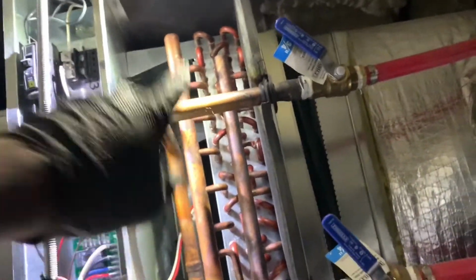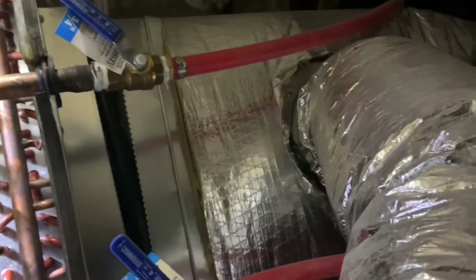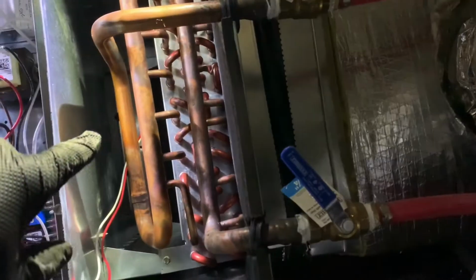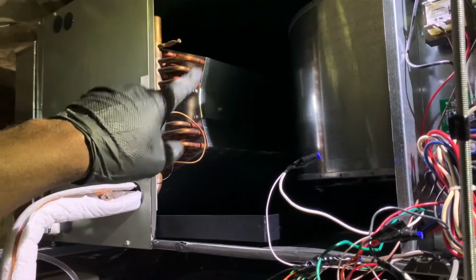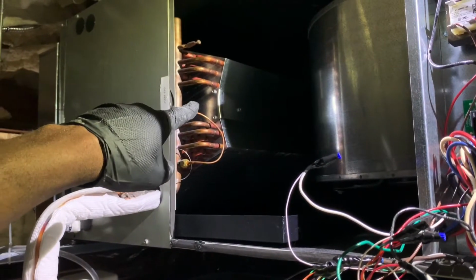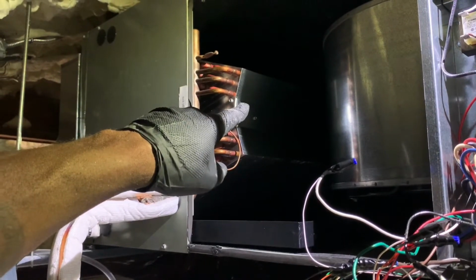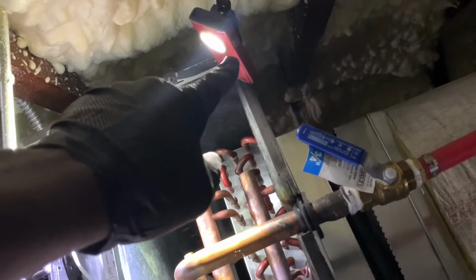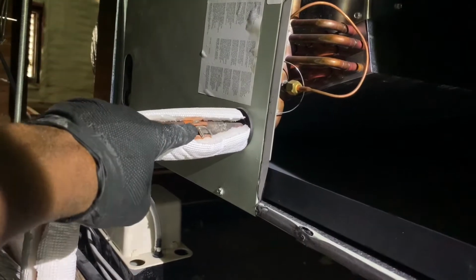Okay, so this is a hot water coil unit. It's a hot water coil right here. It's connected by PEX tubing. And this here is also a heat pump. Okay? The condensing unit is a heat pump. And this is my little light, Nebo. I love it. All right. And this unit has a TXV in there as well. There's an equalizer line with a TXV, and a sensing bulb right here.